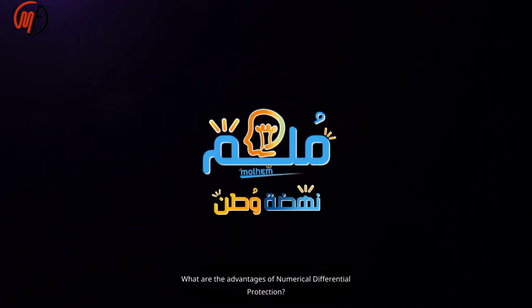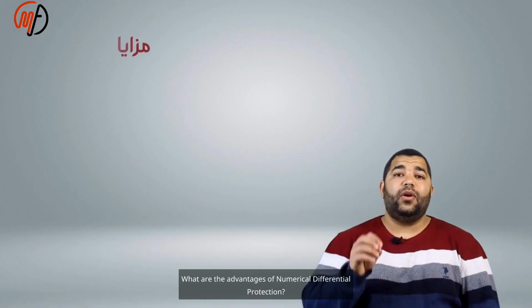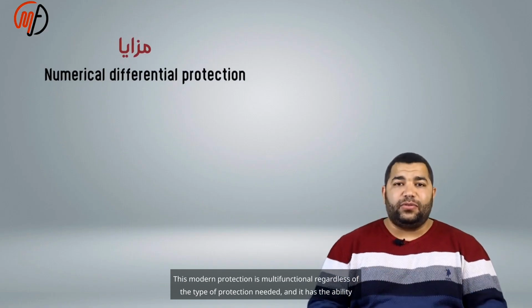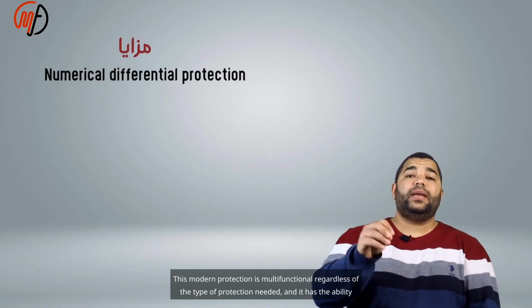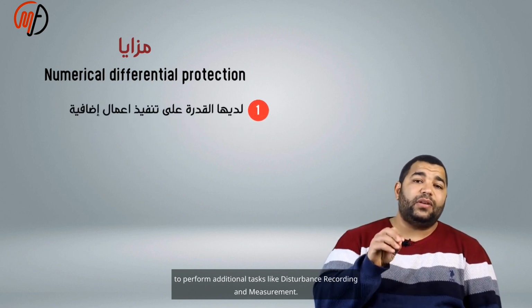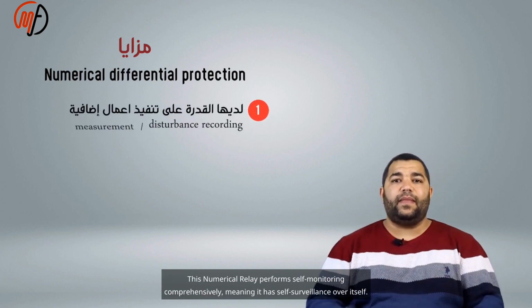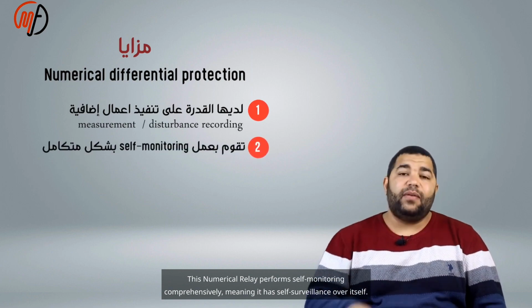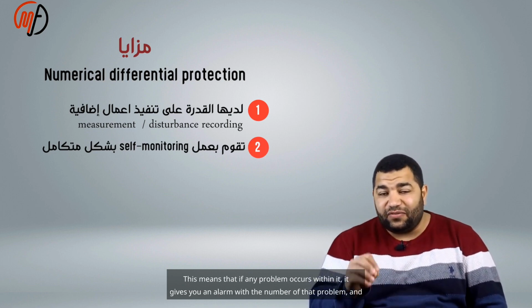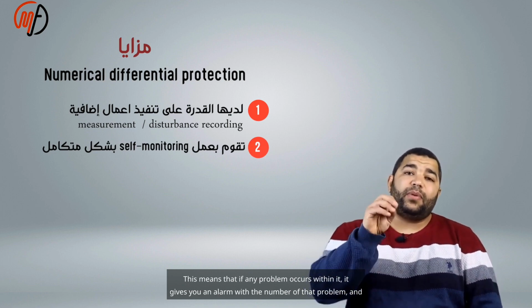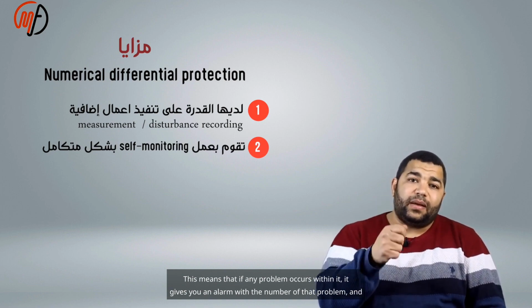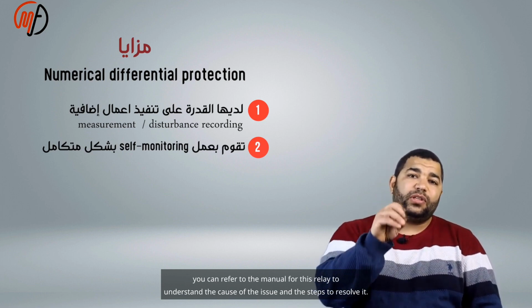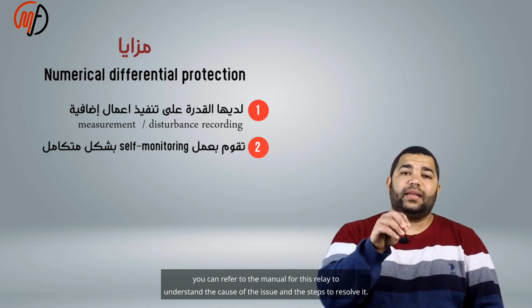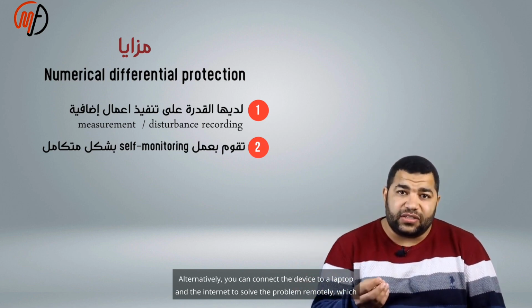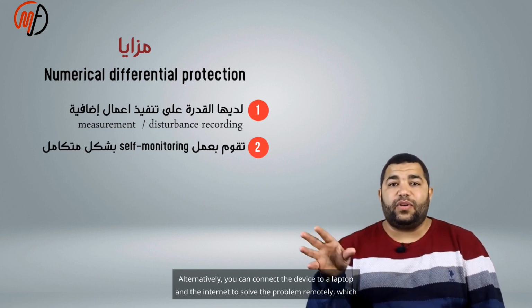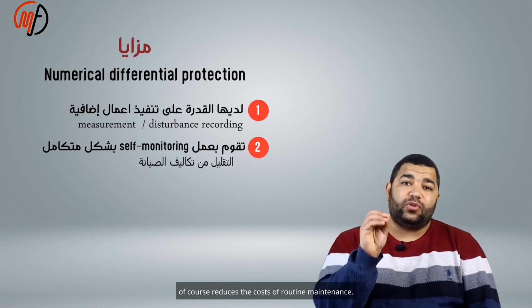What are the advantages of numerical differential protection? This modern protection is multifunctional regardless of the type of protection needed, and it has the ability to perform additional tasks like disturbance recording and measurement. This numerical relay performs self-monitoring comprehensively, meaning it has self-surveillance over itself. This means that if any problem occurs within it, it gives you an alarm with the number of that problem, and you can refer to the manual for this relay to understand the cause of the issue and the steps to resolve it. Alternatively, you can connect the device to a laptop and the internet to solve the problem remotely, which of course reduces the costs of routine maintenance.